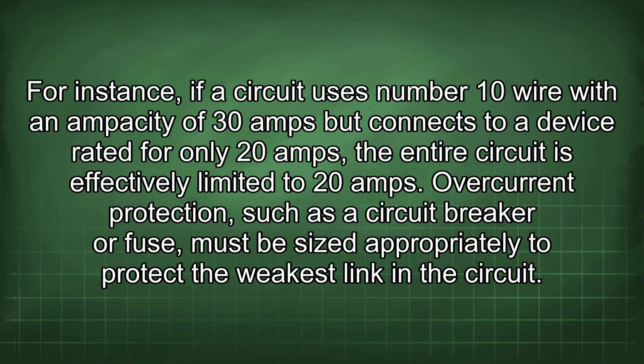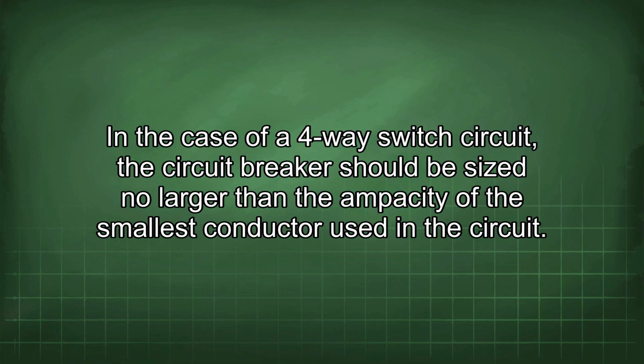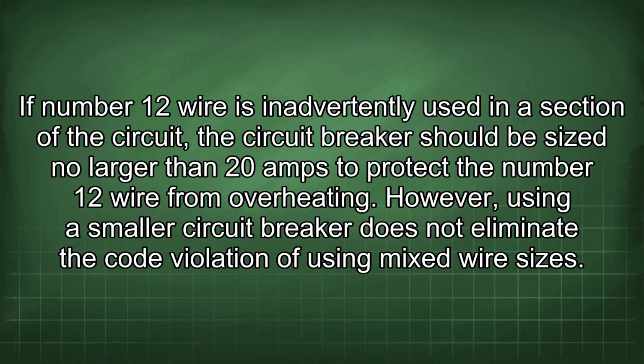Overcurrent protection, such as a circuit breaker or fuse, must be sized appropriately to protect the weakest link in the circuit. In the case of a four-way switch circuit, the circuit breaker should be sized no larger than the ampacity of the smallest conductor used in the circuit. If number 12 wire is inadvertently used in a section of the circuit, the breaker should be sized no larger than 20 amps to protect the number 12 wire from overheating.